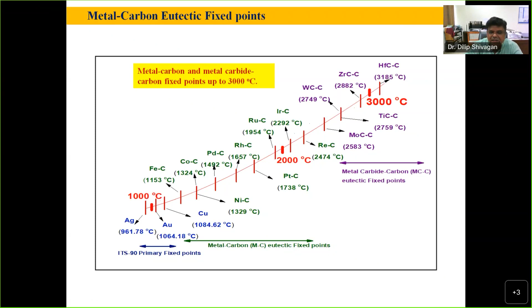So this is on the fixed point. During melting, the fixed point receives the latent heat of energy and remains stable. After it completely melts, it goes to the furnace temperature. Again for freezing, it is a very stable long plateau that you get. The corresponding EMF is measured at, say, copper, which is 1084 degrees Celsius. This way we calibrate at different fixed points and generate the interpolation equation.